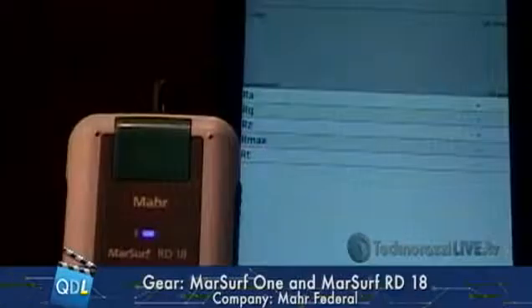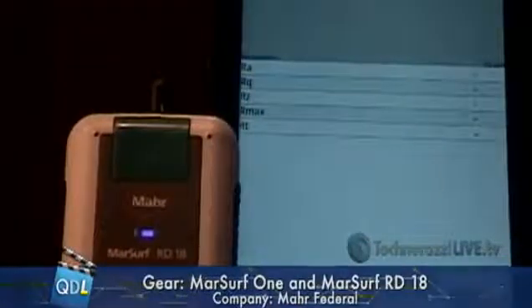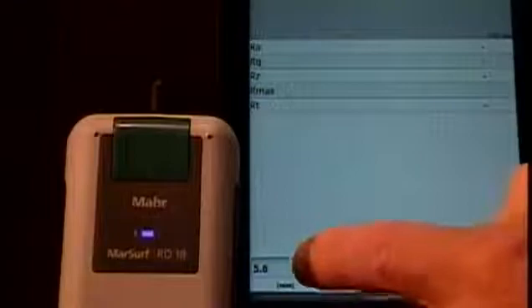And that's it — I am actually ready to start taking measurements right now. In the lower right corner you see a little play button. I press that and now it's going to start taking the scan. As I'm talking, it's taking the scan and drawing me a little trace, capturing my data across the screen. In the lower left corner you see 5.6 — that is the travel distance for the probe. I can select any travel distance up to 17.5 millimeters, the travel length of the skid on the RD-18. I have it set to 5.6 just to keep the scan short.